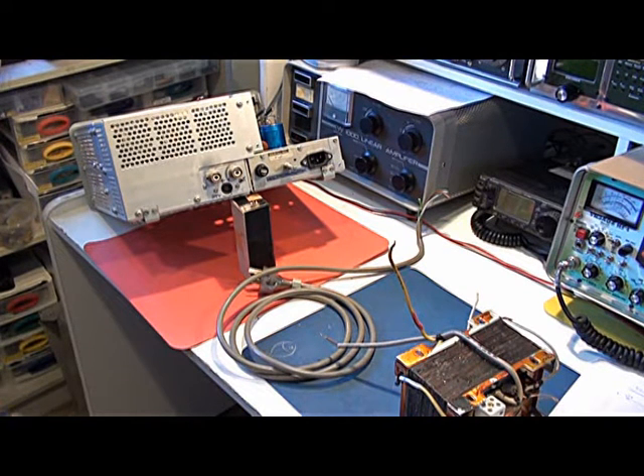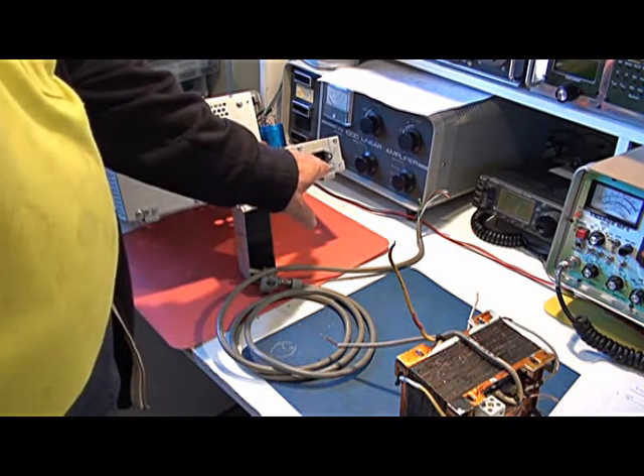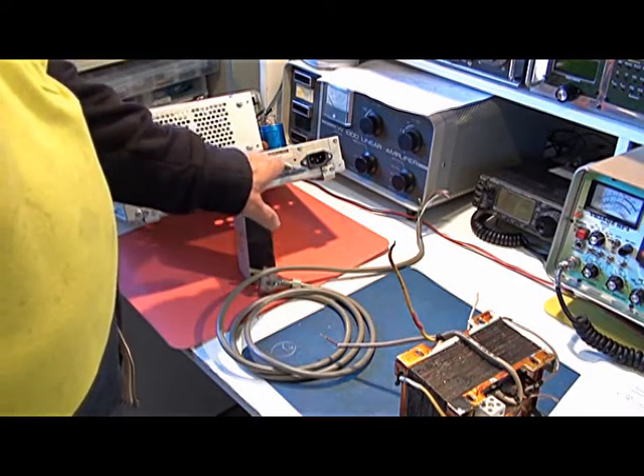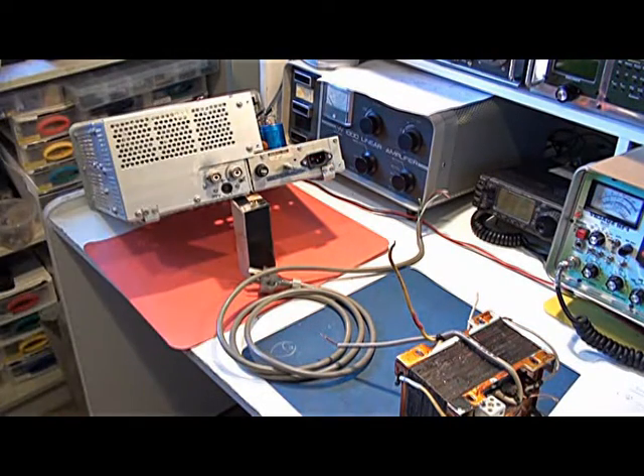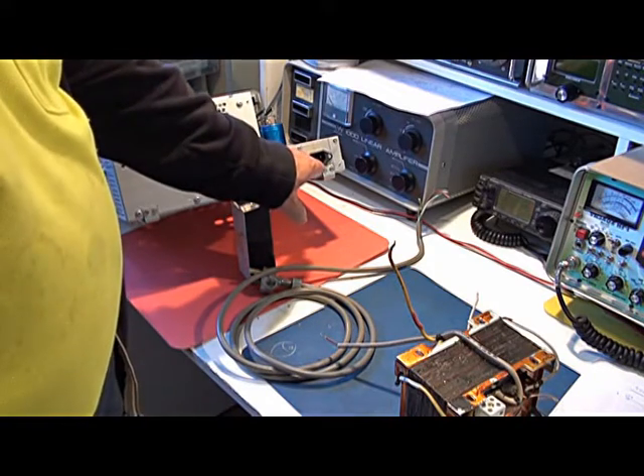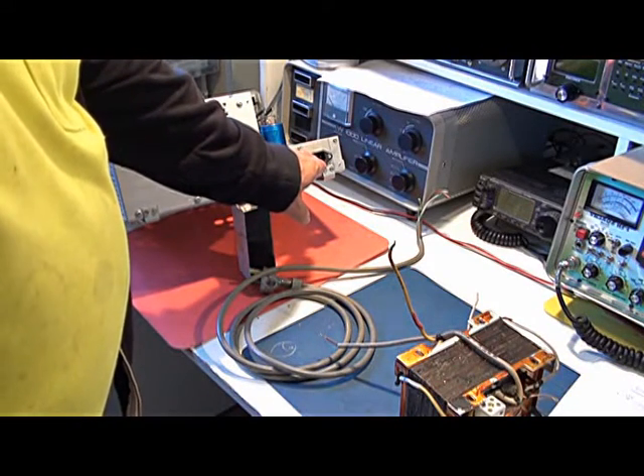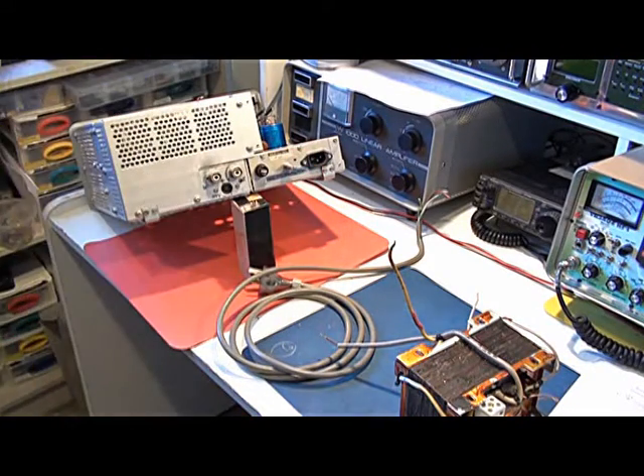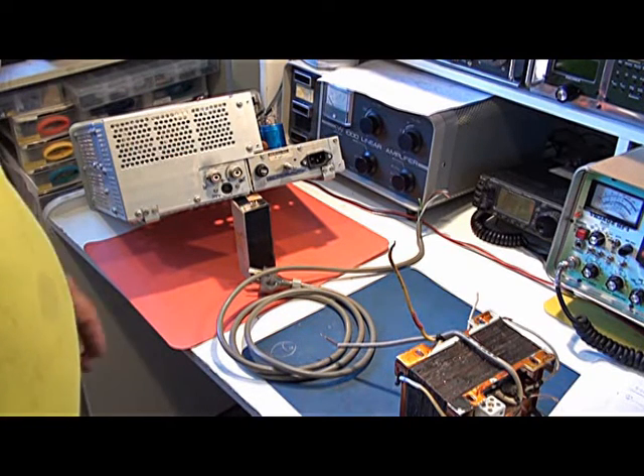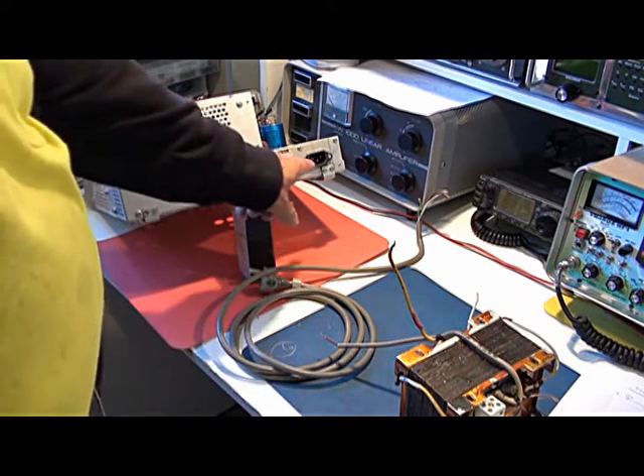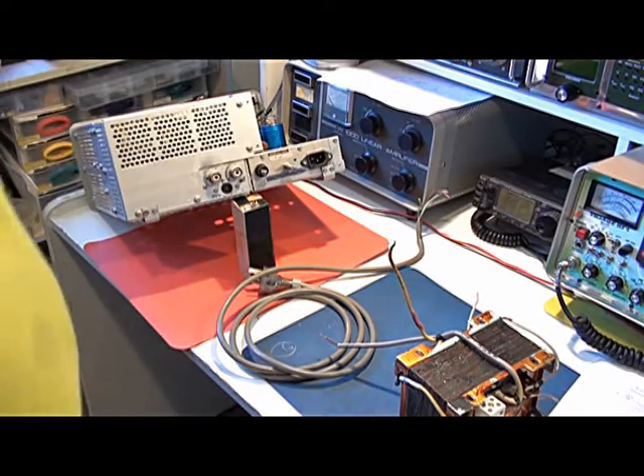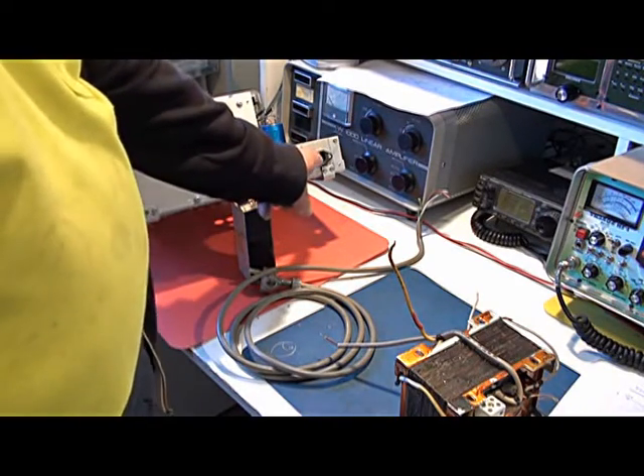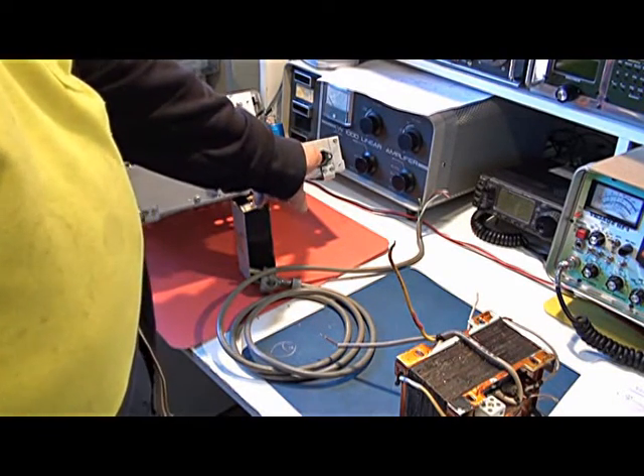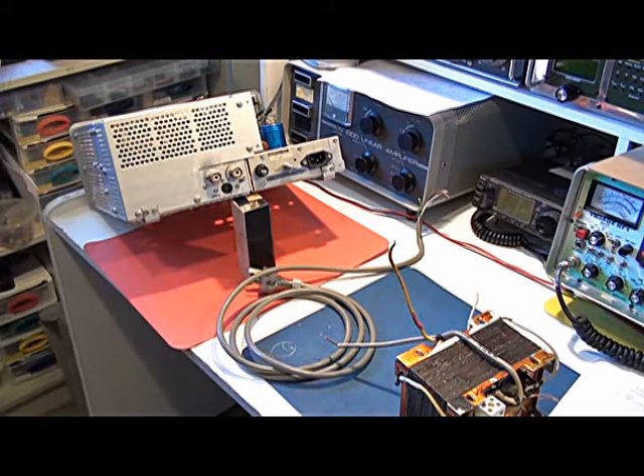Briefly, some of the tests are that there has to be less than 1 ohm between the earth pin and the case, and it needs to be able to take 20 amps of current for at least 1 second. Secondly, the leakage has to be less than 5 milliamps from any of the live parts to the case. Thirdly, there has to be no less than 1 meg of insulation resistance, tested at 500 volts between the incoming supply and the case.